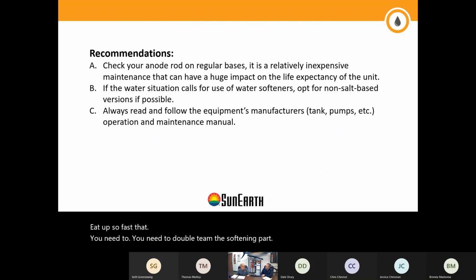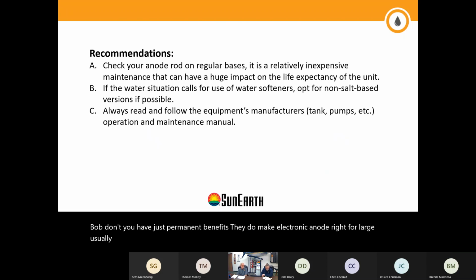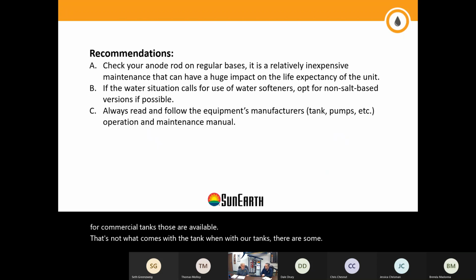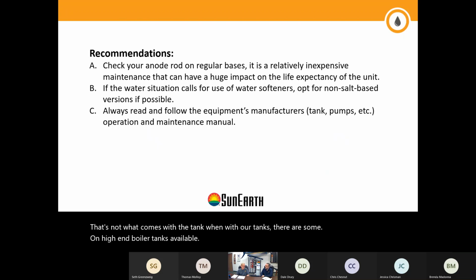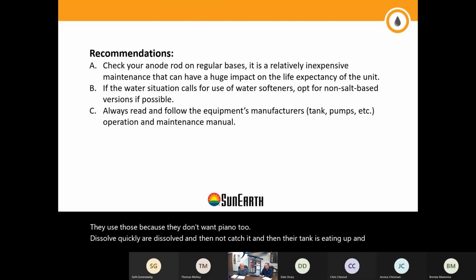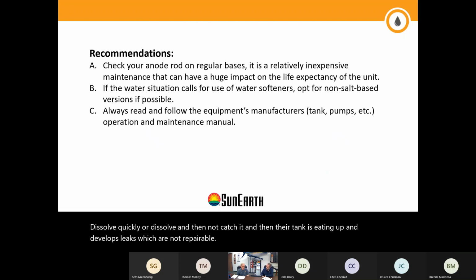And, well, don't we have just permanent anodes? They do make electronic anodes, usually for large commercial tanks. Those are available. Look into them. That's not what comes with the tank. There are some on high-end boiler tanks, and they use those because they don't want the anode to dissolve quickly and then not catch it, and then the tank is eaten up and develops leaks which are not repairable. Once a vessel is leaking in the vessel itself, it's generally not repairable. You have to replace it. So we want to avoid that.